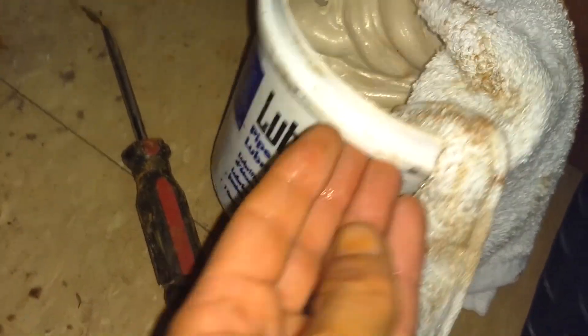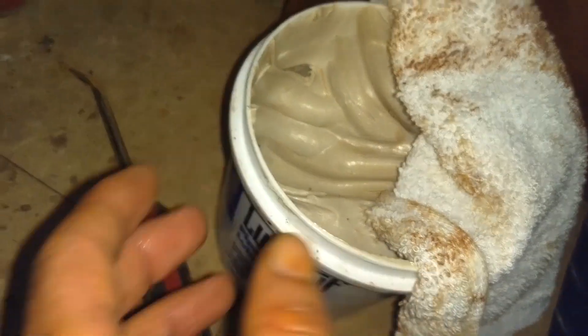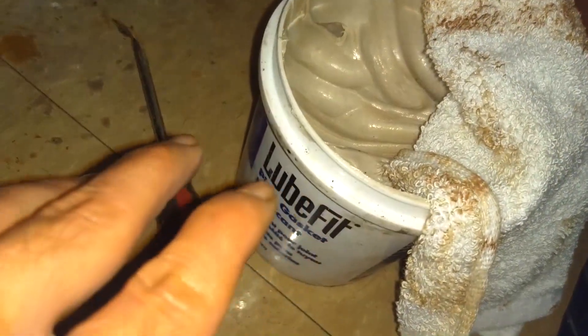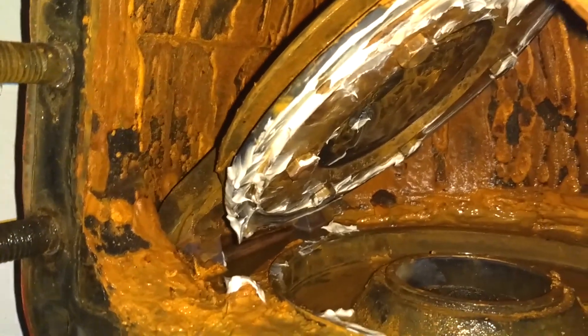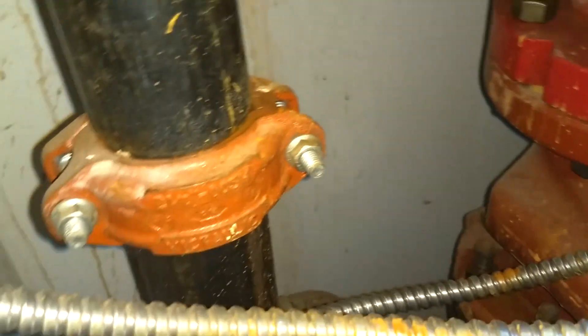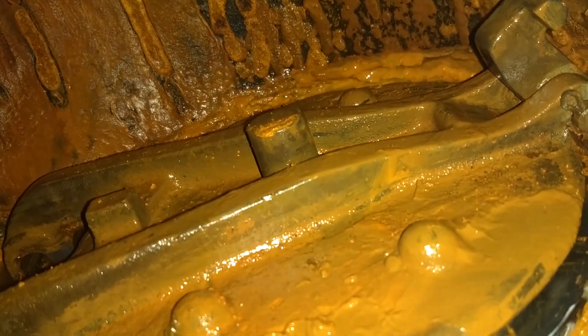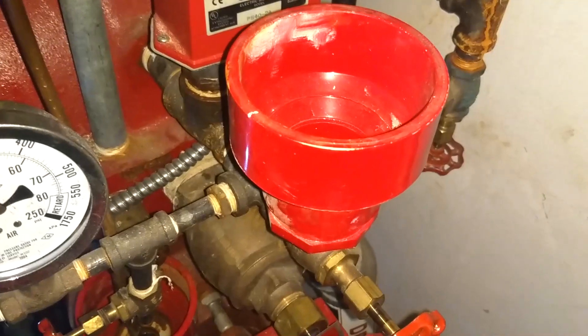If you can't get your gasket to seal, put some water-soluble lubricant on there — it's going to dissipate once water hits it. Don't recommend any sealant. With that water-soluble lubricant on there, it should stop the water from seeping past the clapper into the intermediate chamber.